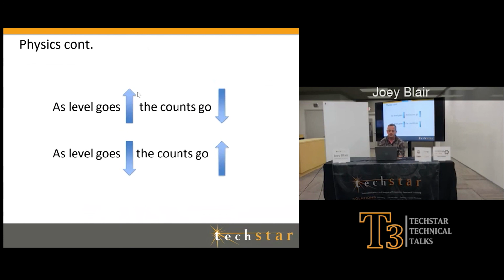So it makes sense if all my detector is doing is reading the radiation, and it sees a lot of radiation over here, then that means there's nothing blocking it. There's absolutely no level in that vessel blocking that radiation. That's why it's seeing a lot of radiation. As I start to fill, I'm now blocking all of my radiation. So if I'm reading it over here, I'm not going to see much. It kind of helped me when I was first learning to think of it that way. Just as my level goes up, counts go down. As level goes down, counts go up.